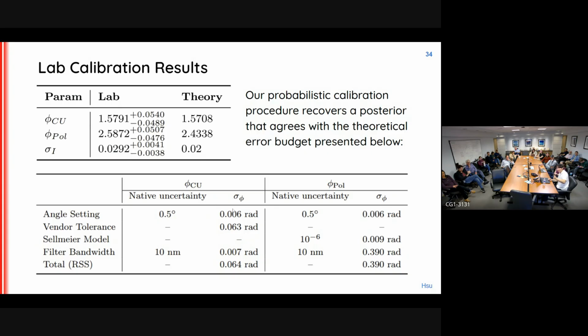The right column is the propagated uncertainty into the retardance angle space. There's the angle setting, because I rotated them manually. So there's a native uncertainty of 0.5 degrees, and then you can see that propagate to like 0.006 radians. There's the vendor tolerance, and that actually only applies to the calibration unit because we're using that one at its operating wavelength. It doesn't really apply to the polarimeter.